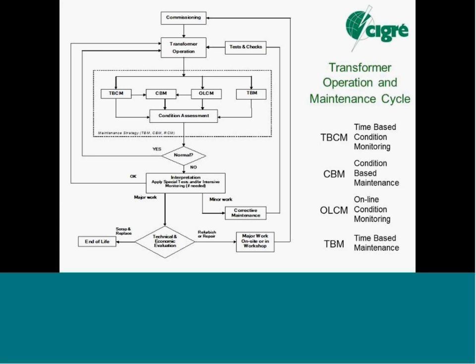Clear at the top, commissioning a new transformer, putting the transformer into operation. Have below that the large rectangle surrounded by a broken line rectangle, surrounding those four elements of maintenance strategy. See the acronyms there and what they are in wording at bottom right. Now, time-based condition monitoring, one on the left, feeds condition-based maintenance, as does online condition monitoring. So that's deliberate, that we don't do condition-based maintenance without having done some condition monitoring.